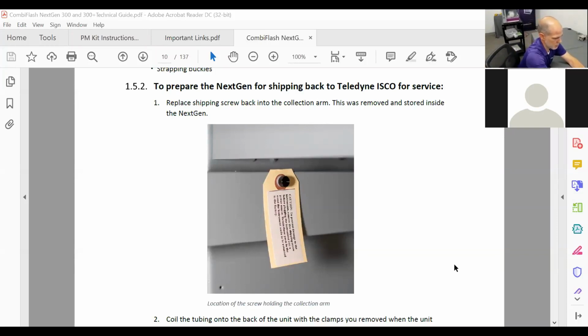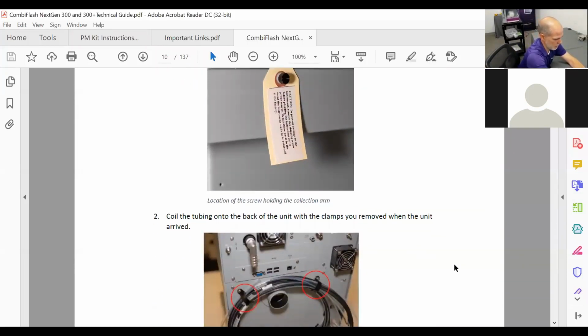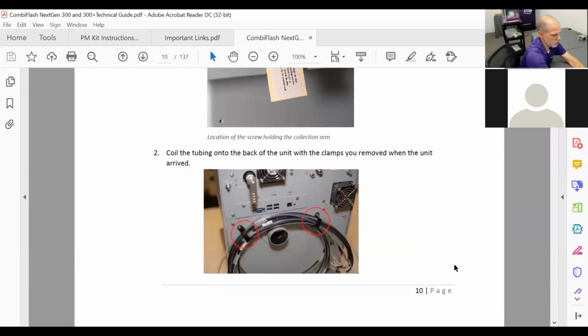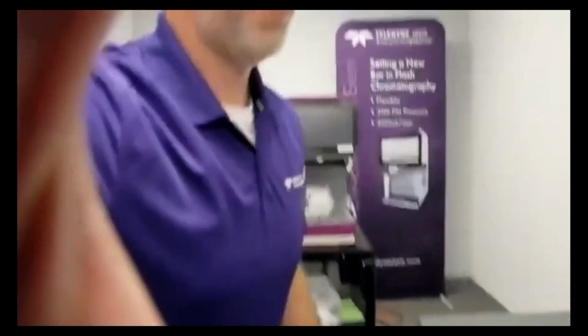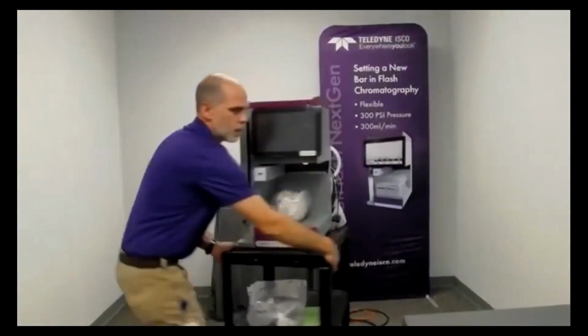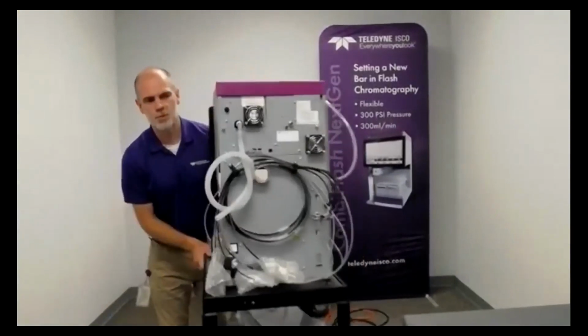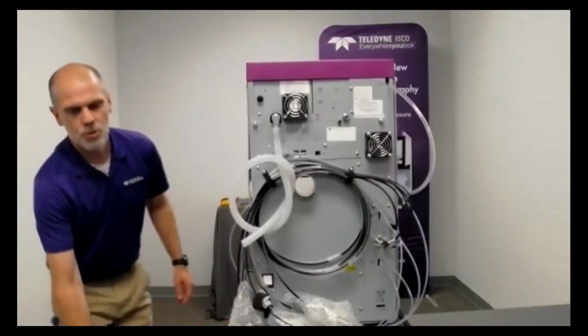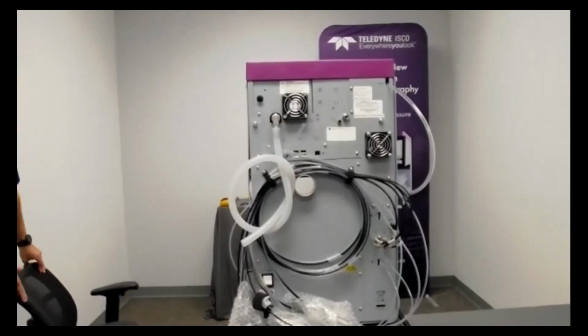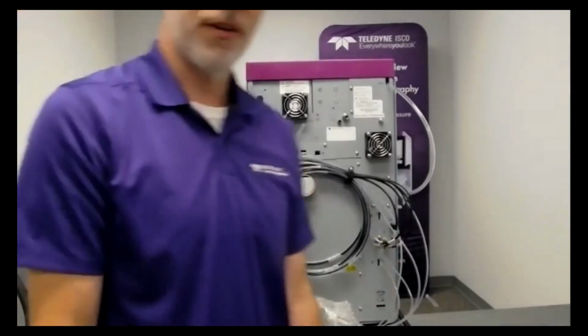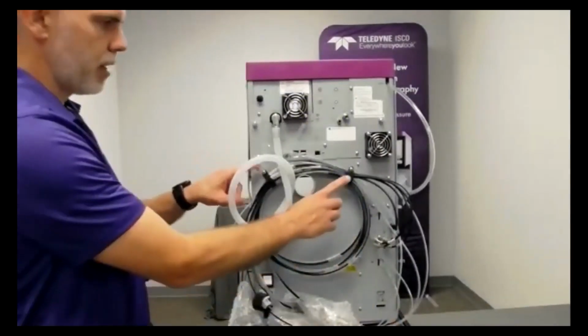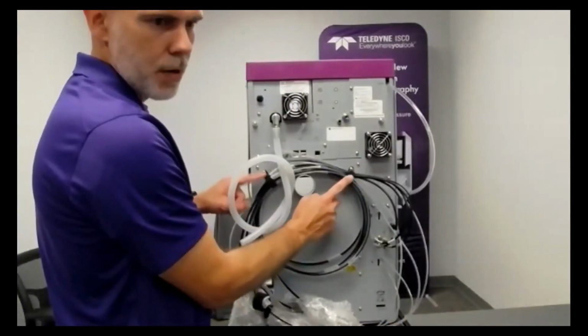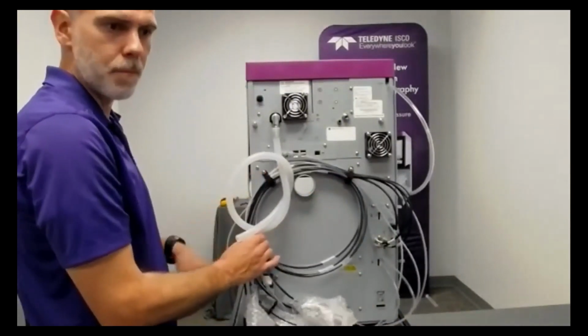So that was the shipping screw. Next, you're going to need to coil the tubing into the back of the unit with the clamps you removed when the unit arrived. So I'll show that to you real quick. What we're talking about is right back here. So if you do an install for a customer or for yourself, don't get rid of these black loops here that hold the coils in.